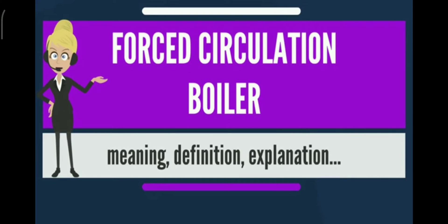In a water tube boiler, the water is recirculated inside until the vapor pressure of the water overcomes the vapor pressure inside the steam drum and becomes saturated steam. The forced circulation boiler begins the same as a natural circulation boiler, at the feed water pump. Water is introduced into the steam drum and is circulated around the boiler, leaving only as steam.